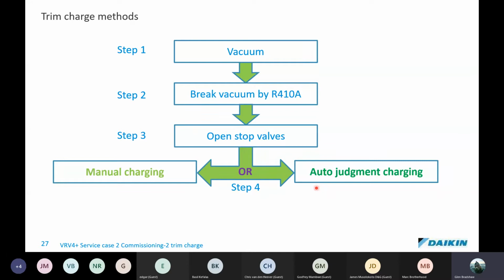Right, so let me just go back on that. Breaking the vacuum with 410A: if the charge is less than 5 kgs, we will tend to charge the full amount. If it's greater than 5 kgs, then we will look at doing a manual charge or an auto judgment charging. But we'll always break it with some of the refrigerant, just to make sure that we don't suck any air into the system.